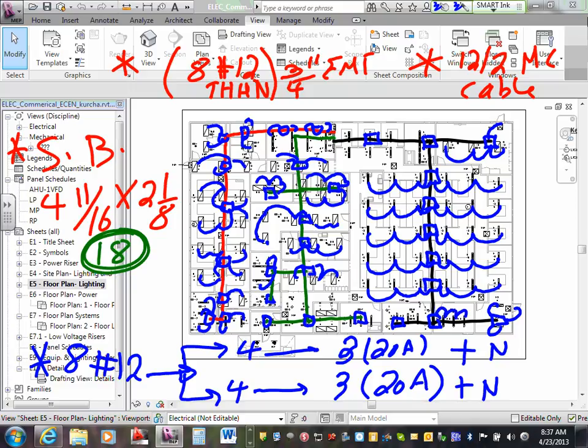Then I went down here, guys. When you put these boxes, you don't want to carry more than 6 fixtures. You don't want to bring more than 6 cables to this, because if you bring more than 6 cables, here's what's going to happen, guys. You're going to overload this box in terms of number of conductors. So when you come over here, here's what I did. I have a junction box, same thing right in here. I went from fixture to the box. I could have done fixture, MC cable to box, fixture to the box.